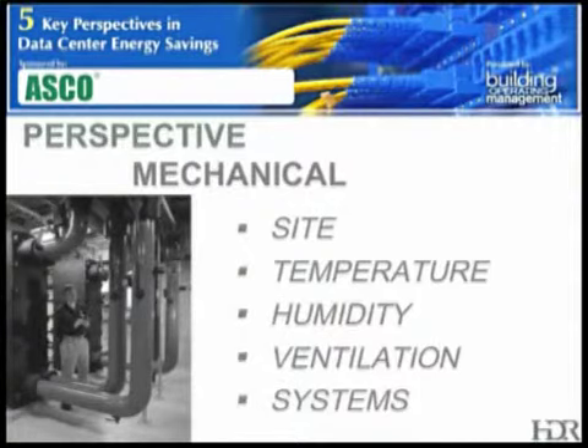Matter of fact, even in some locations here in the Bay Area, we've got a lot of compressorless data centers, running exclusively on either economizer or in some cases economizer supplemented with some evaporative processes. I think, again, it's a combination, as Craig said before, of looking at what the site provides versus what your operating class is going to be within the data center. And humidity, again, the humidity range has also been expanded vastly by these criteria.